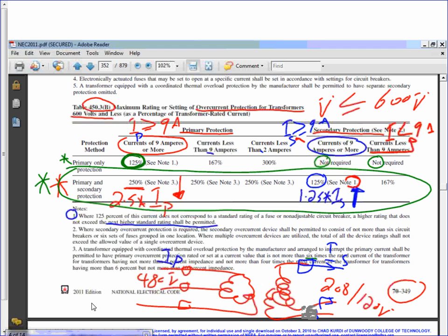Can I get you guys to look at this? Wherever you see note number 1 in the table, that's where you go up. Can you guys see that? You go up wherever you see note number 1. Are there any note number 1 here? No. So can you go up here? No. So on the primary side, we go down. On the secondary side, we go up. One more time. On the primary side, we go down if it's not standard. On the secondary side, we go up. Why do we go up? Because this has note 1. This does not have note 1. It's not related to going up.